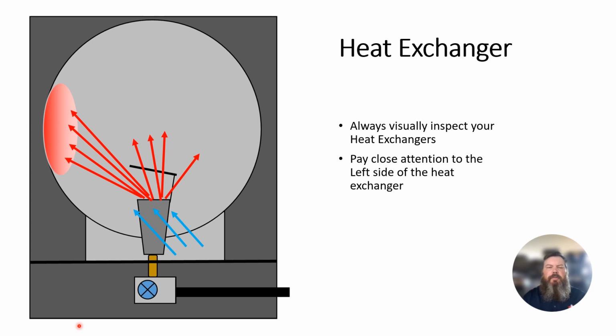This is a cutaway of a mobile home furnace, and we're looking straight down on top of the burner. The way these are designed, they have a combustion air blower over here on the right. It blows air into this heat exchanger through the burner from a path from right to left.